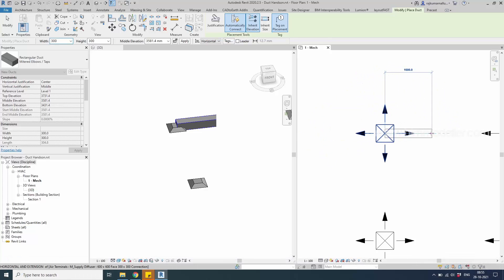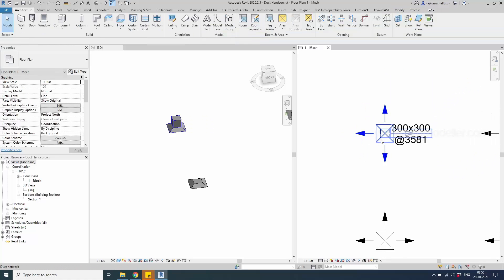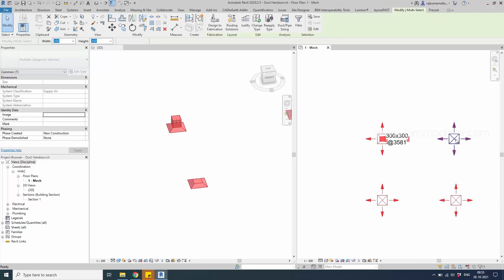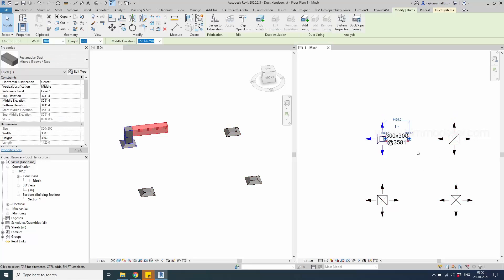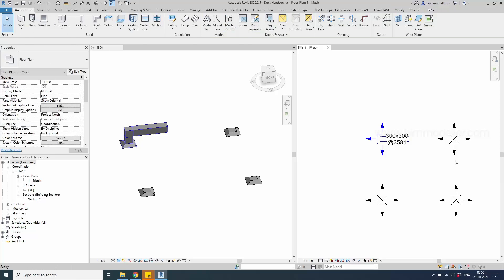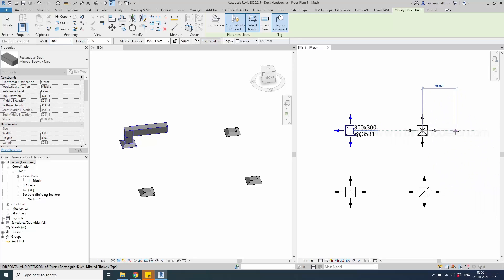If you click this button, it will show the duct in the same place. However, if you use the 'Inherit Elevation' option, Revit automatically creates the duct at different heights. Create a duct, click the position, and while modeling use 'Inherit Elevation' to create them automatically at the correct heights.